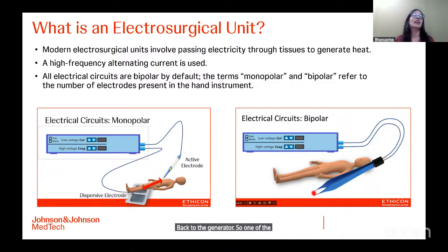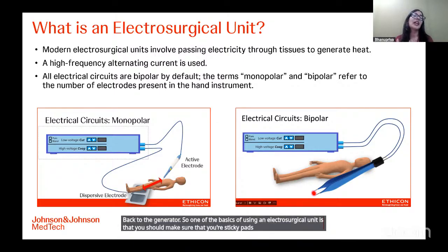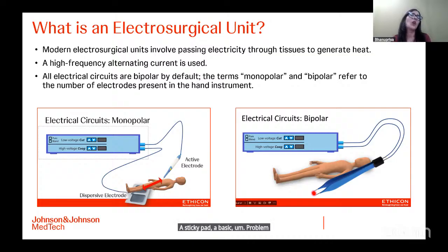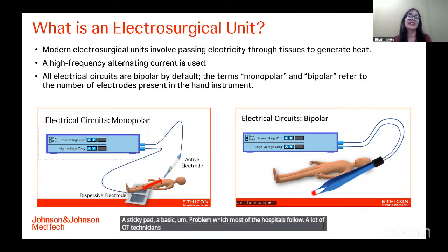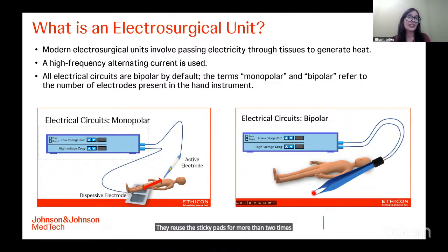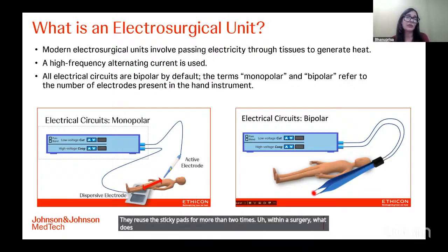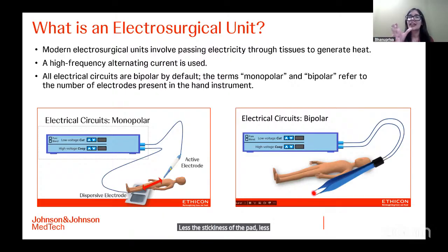So one of the basics of using an electrosurgical unit is that you should make sure that your sticky pad, or return electrode, is always there. A basic problem which most hospitals follow, and a lot of OT technicians do, is that they reuse the sticky pads more than two times within a surgery. What does this lead to? The stickiness of the pad reduces with the number of usages of the same pad. Less stickiness means less area of contact with the surface of the patient. Less area of contact means the pad is not able to suck away all the current which is there in the patient.